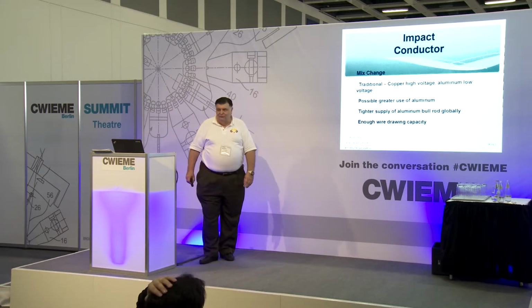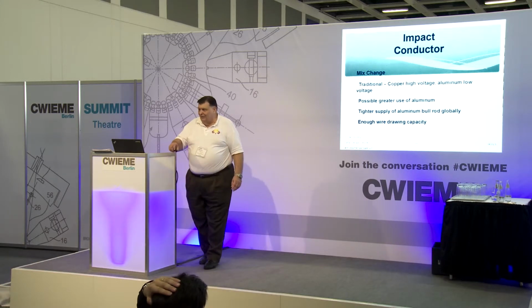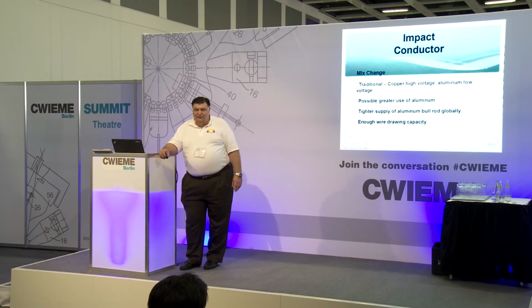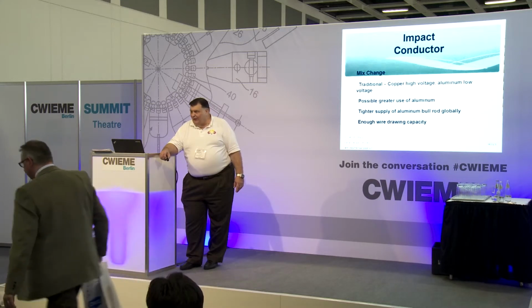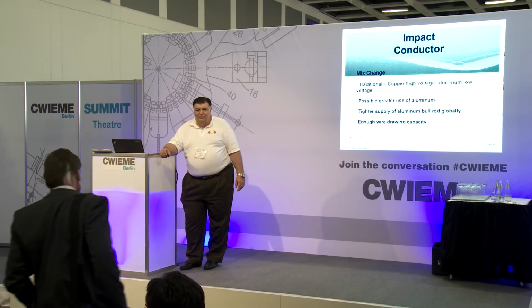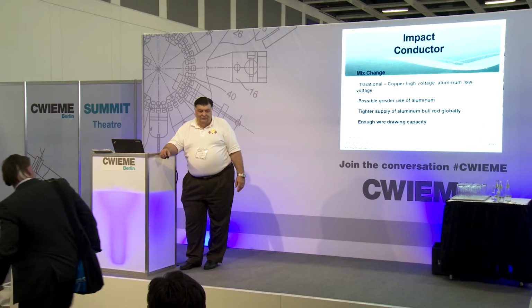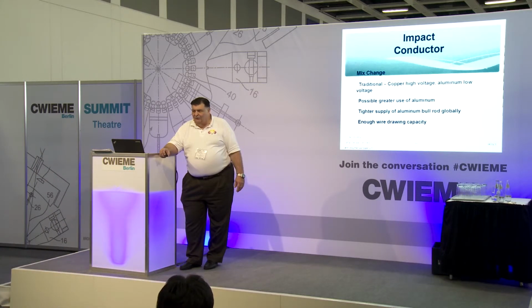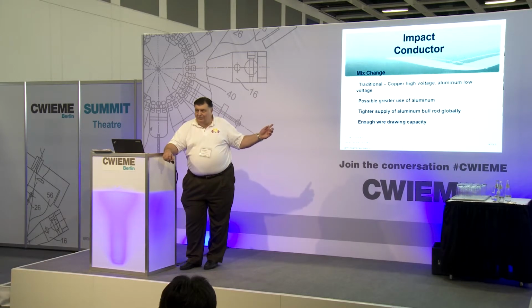And then, is there enough wire drawing capacity? Most plants that draw magnet wire draw both aluminum and copper magnet wire on the same equipment. Everyone talks about magnet wire capacity in copper equivalent pounds, and that's fine, but it takes 3 times the time to draw a pound of aluminum that it does to draw a pound of copper.